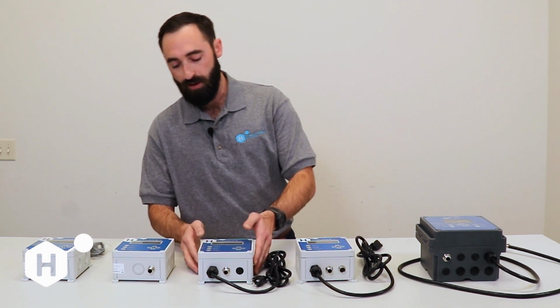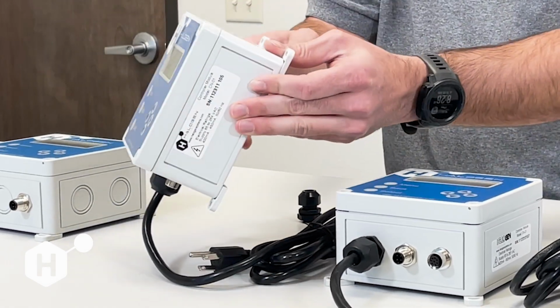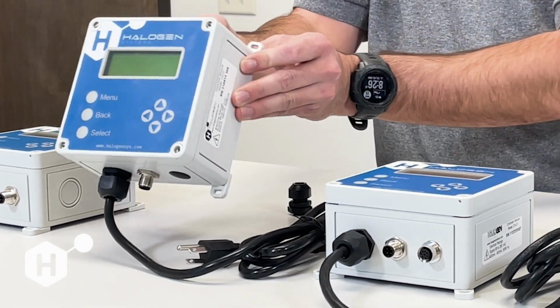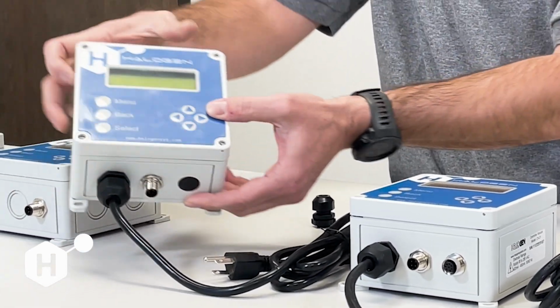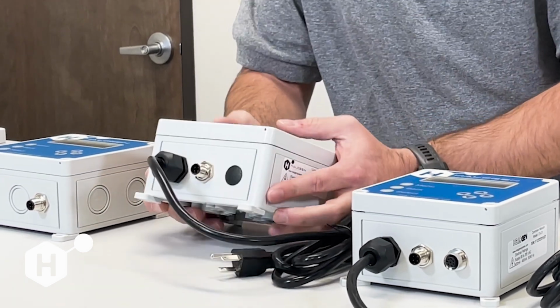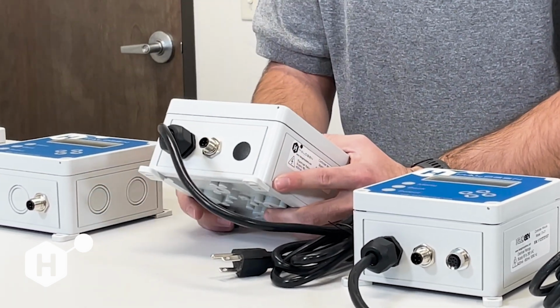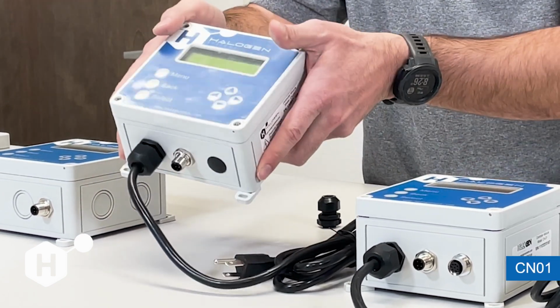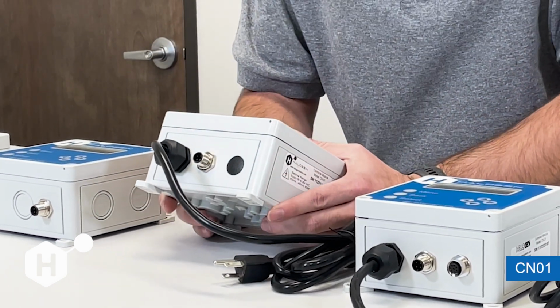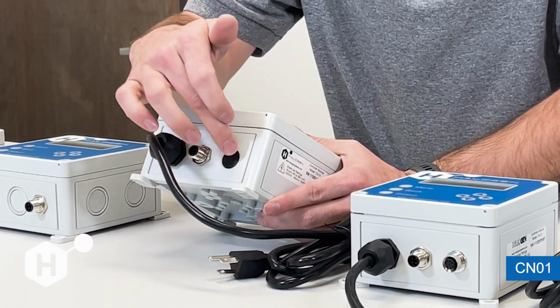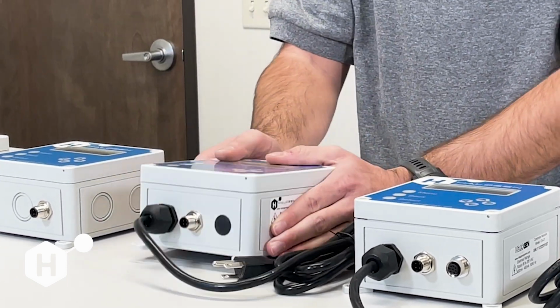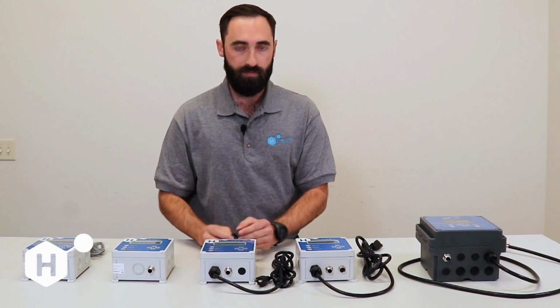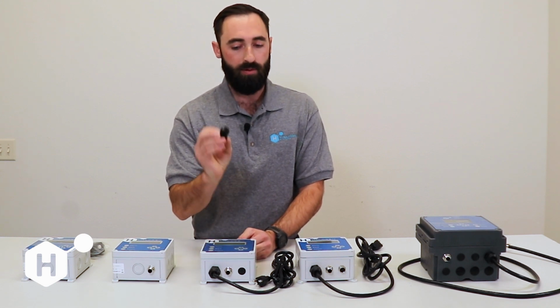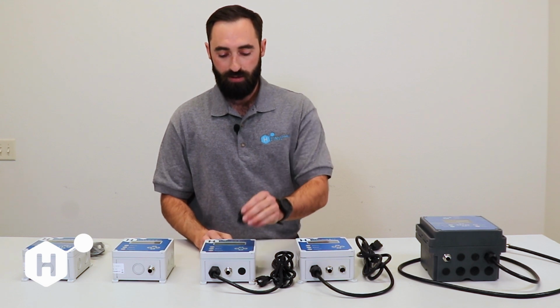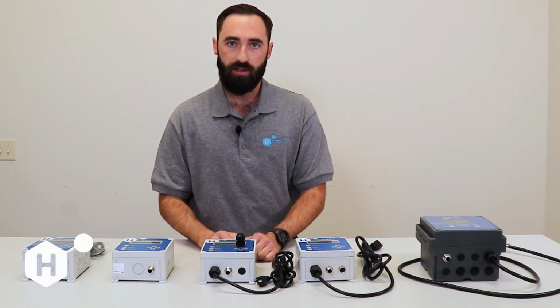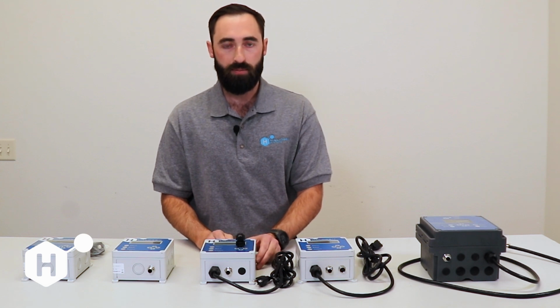The other interesting thing about these is, as you can see, there are no knockouts on the enclosure. It's just a smooth enclosure. And what we do is we will pre-drill our M12 sensor connector, and then this is our CN01 model. The CN01 model comes with a pre-drilled hole plugged here, so that you can install either hard conduit or a PLC cable with the included strain relief here. We ship each one of these CN01s with one strain relief for installation into the plugged hole here.